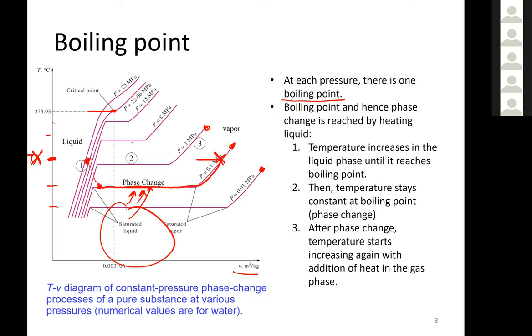So also, again, I go back here to the selection of the refrigerant. We always should make sure that our refrigerant has a critical point that is high enough away from the operational range. So if my operational range, for instance, goes between minus 17 degrees C to, let's say, 40 degrees C, I need to make sure that the critical temperature is much higher than 40 degrees C in order to avoid basically having supercritical phase. And I need to make sure that my operation is going to be between these two basically subcritical pressure values.